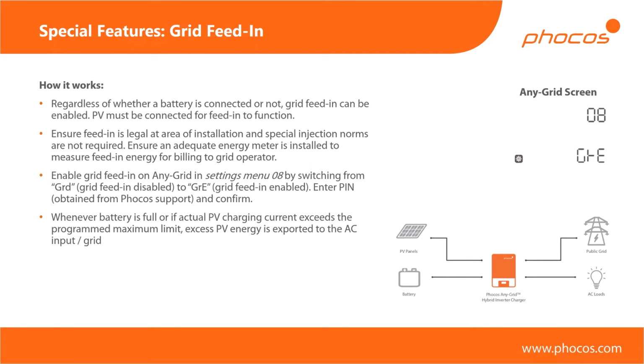And then one of the last special features I just want to outline here is the grid feed-in, because we don't have that much time left. We have about half an hour left. We have the grid feed-in feature. I think it's obvious what it does. As soon as you have more power that you can either use to charge your battery or to power your loads, that means you have excess power, and then you can sell that power to the grid. In order to do that, you go into settings menu number 8 to enable grid feed-in, and you will require a PIN, and this is important so that you don't activate it by accident. A lot of grid operators would be very unhappy if you could, and you will get that PIN number. It's a 4-digit number from our support team.